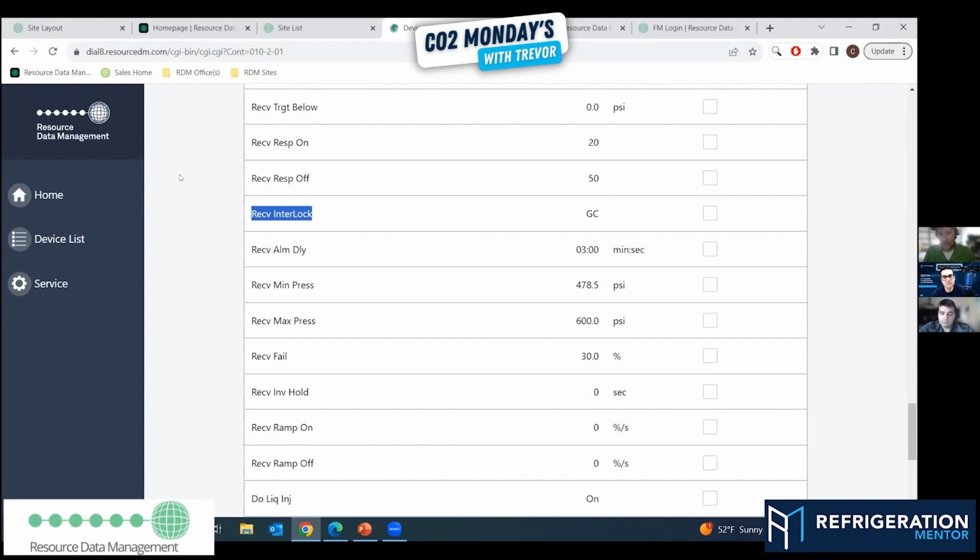The only thing that I see that on the recent update got taken out is there used to be a gas gradient, and you could set up the gas gradient for the certain CO2 we're using. So the UK used a certain gradient on CO2, like they were using refrigerant grade or bone dry or vice versa. Well, they have different grades of refrigerant that these techs are using. It makes a difference in the background of the software because it has different flow rates and different weights to it and so on and so forth. I'm not going to get into the boring details of that, but it does make a slight difference. And you used to be able to come in here and set those gas gradients for what CO2 you were using. They took that out, but it is what it is.